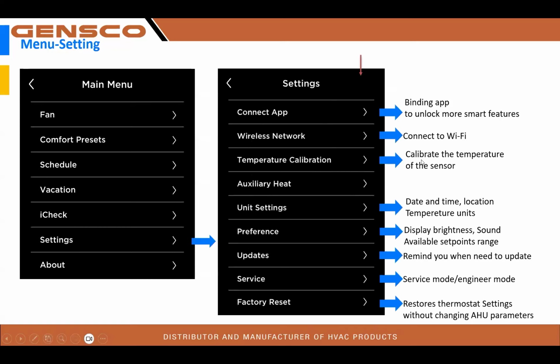This is important. On every thermostat, we're going to install it onto the wall and get it fired up. We want to make sure that the temperature the thermostat is reading is accurate. So we're going to put our pen thermometer or a temp sensor on top of the thermostat, and we're going to walk away for 5 to 7 minutes and let those two see where it's at. If you need to make a temperature offset, you just go into temperature calibration and go up or down to match what your thermometer is reading.